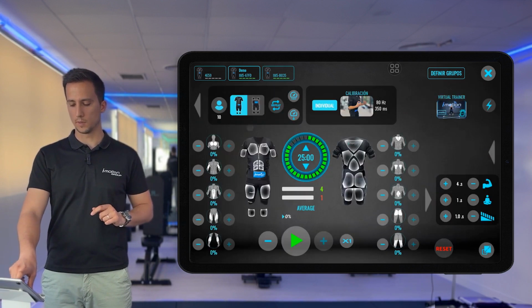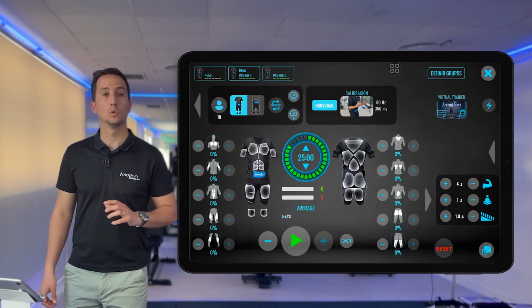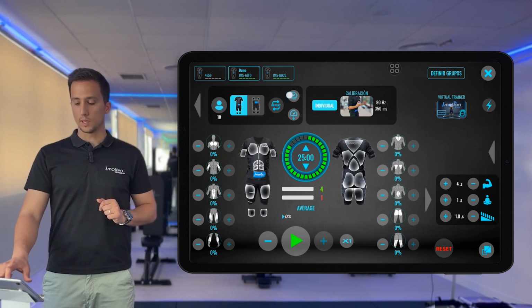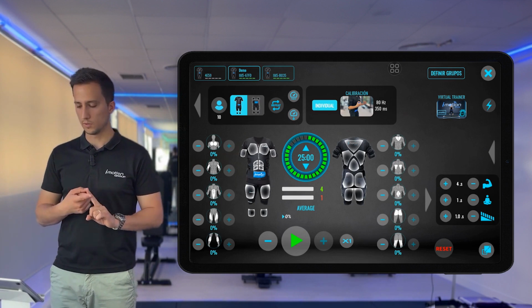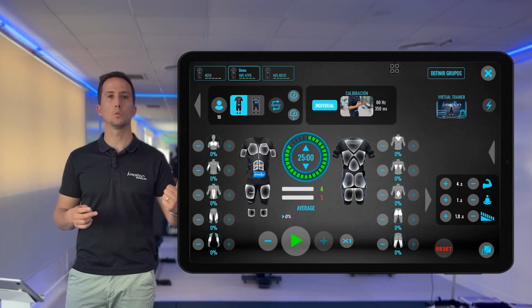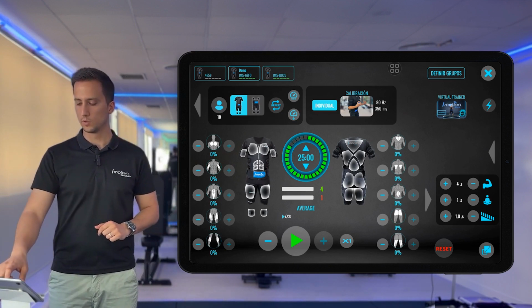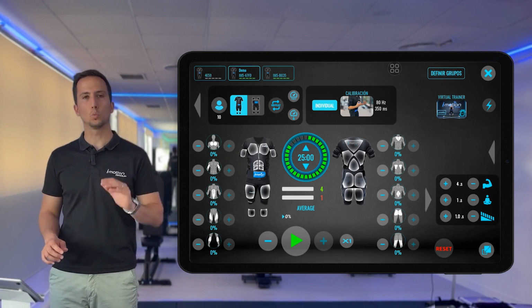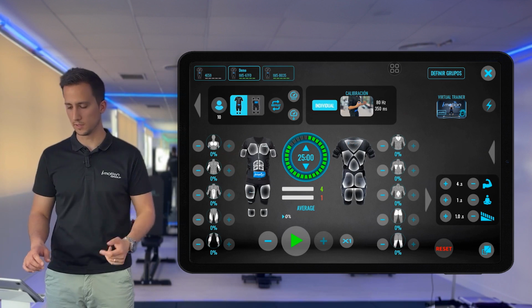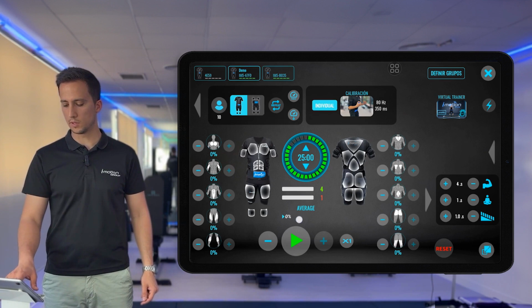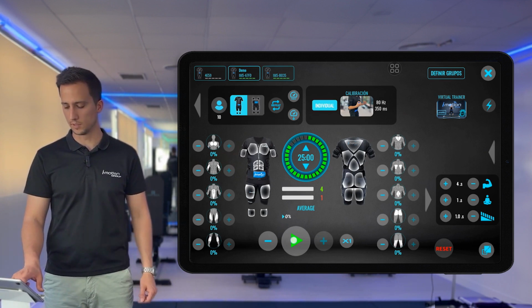For this first time, I will choose calibration to start by performing the calibration. Here we will have 3 buttons. One to save the calibration, one to retrieve a previously saved calibration for a client, and one to repeat a session that a client has already done, allowing us to replicate it exactly the same. Calibration program, I can start the session because I already have my client and my training mode set.